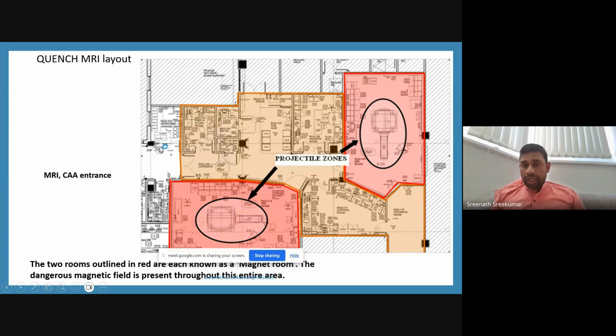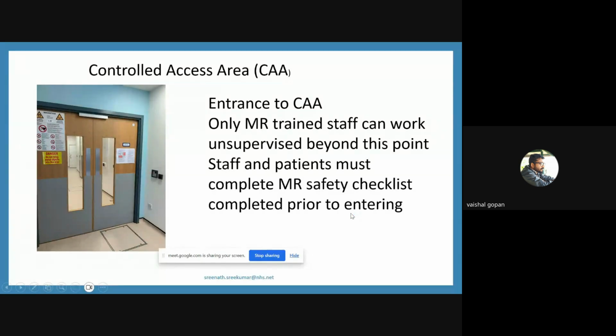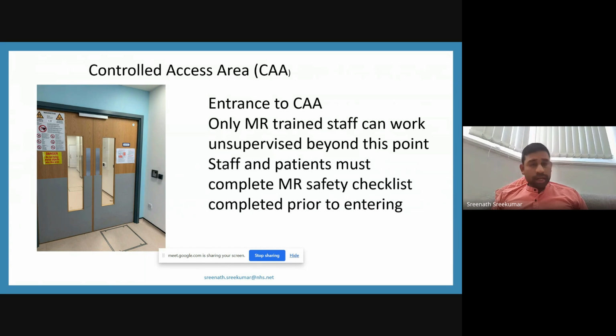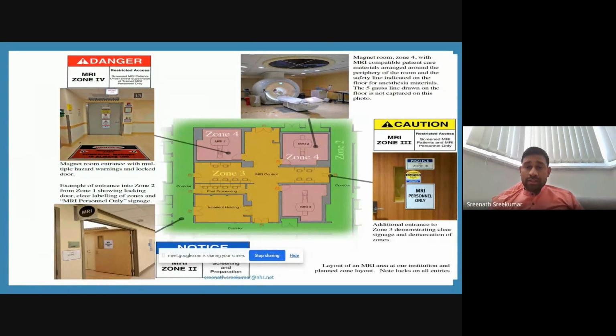Another way of telling this is a quench layout. They will say quench layout because they can see the controlled access entrance here. So this is them coming inside as a controlled access area. We can see clearly the boundaries we mentioned. This is the controlled access area and the MRI environment is here. In this schematic diagram we can see clearly that when entering a controlled access area, there are pictures put on the door, and there are also swiping cards or passwords for staff who are allowed to go inside without any screening. Other staff will not be allowed to go inside, nor will patients, without completing a safety checklist. This is also another way of telling zone 1, zone 2, zone 3, zone 4.